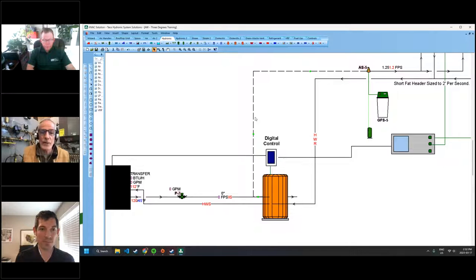And anytime you move through a tank, you're going to stir up that tank a little, because unless those flows are exactly the same, there's going to be movement in that tank from top to bottom. So you lose the ability to stratify the water. You lose the ability to really use the exergy of that tank 100% when you use a 4 pipe. So a 2 pipe is a way around that.